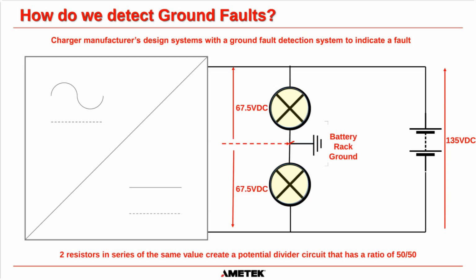So as you can see, if you measure between the positive point of the charger to ground, you're going to get 67.5 volts DC. And if you measure between the negative potential and ground, you're going to get 67.5 volts DC with a 135 volt DC battery. Obviously 67.5 and 67.5 equals 135. If we lifted this terminal here, this charger would go back to floating operation and it would have no reference to ground whatsoever, just like I'd shown you before. It's only because we have added this ground fault detection circuit that we have now virtually tied the ground to the halfway point of the battery.